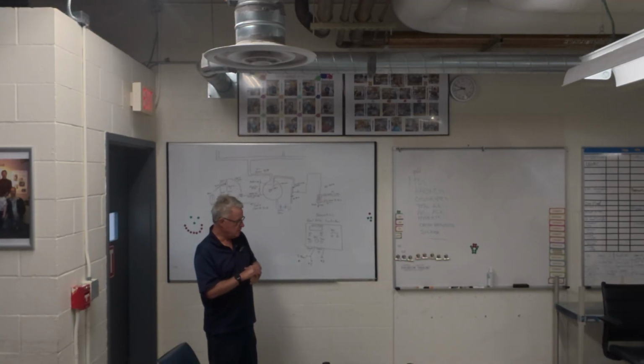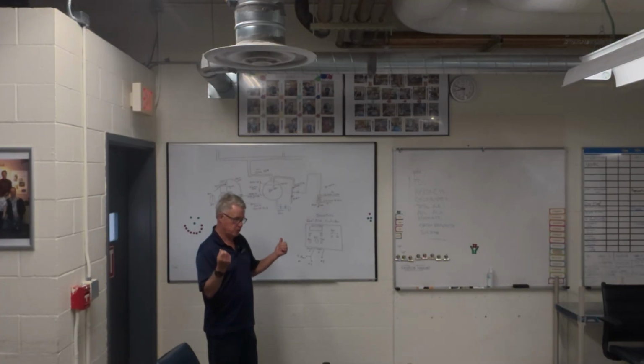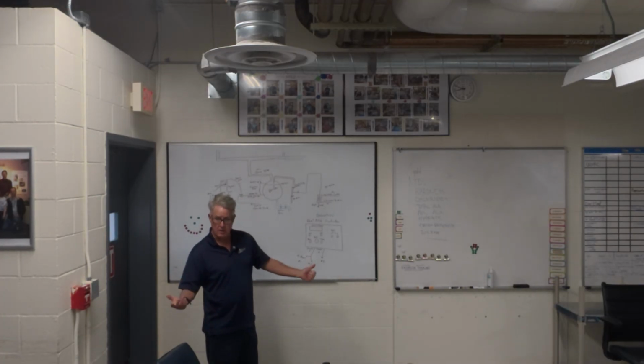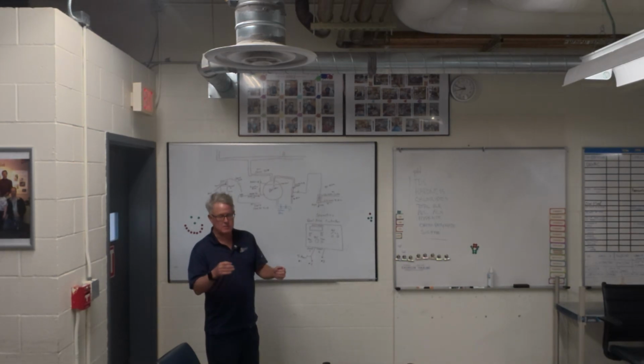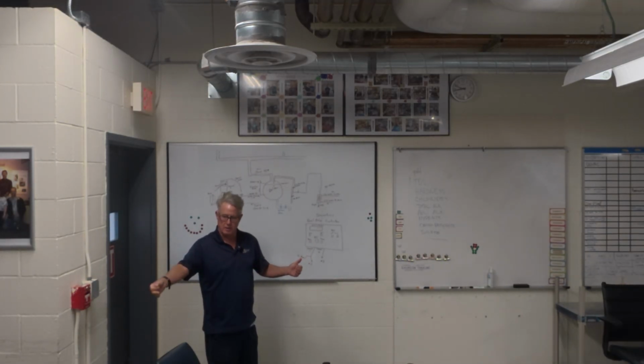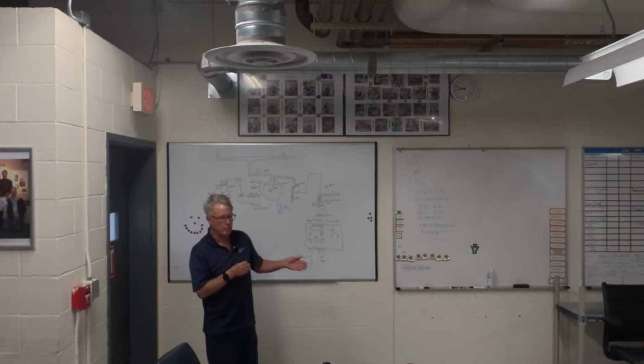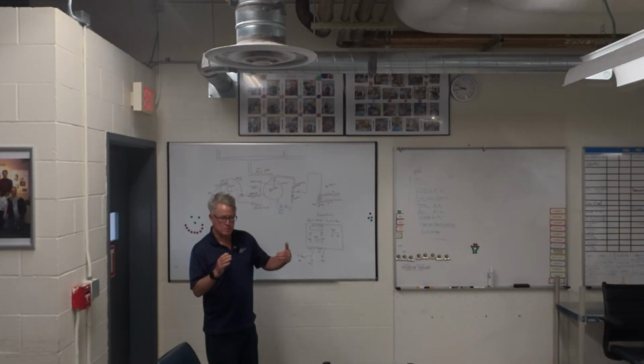There are three types of steam line chemicals: morpholine for short line, DEA for long line, and cyclohexamine for midline and long line. When I first got here, they were using mostly DEA and a little morpholine, so they weren't protecting the lines all the way to the end. One of the changes we made was to put cyclohexamine mixed with morpholine.